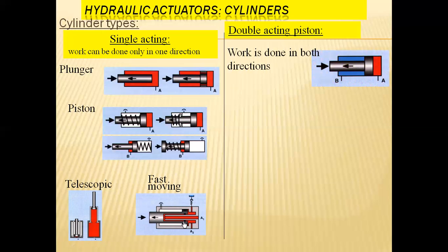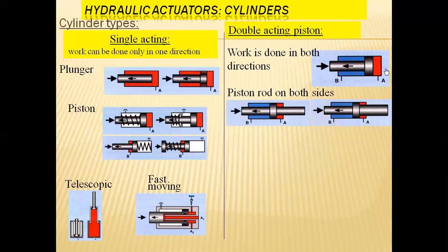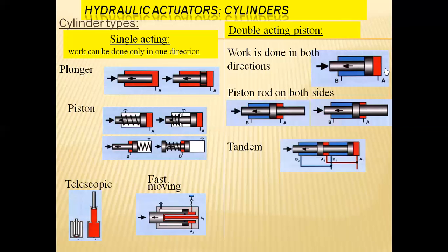In the case of the double acting piston, work is done in both directions. Fluid entering toward side A leads to extension of the piston; when pressure is applied on side B, the piston moves toward the left — the contraction position. With a piston rod on both sides, it can support bilateral movement of fluids from one channel or port to the other, maintaining any number of channels with a single piston.